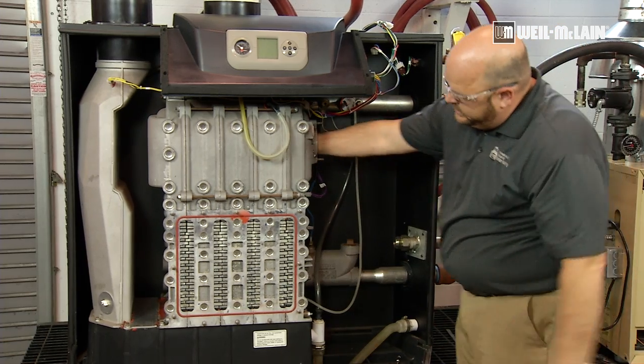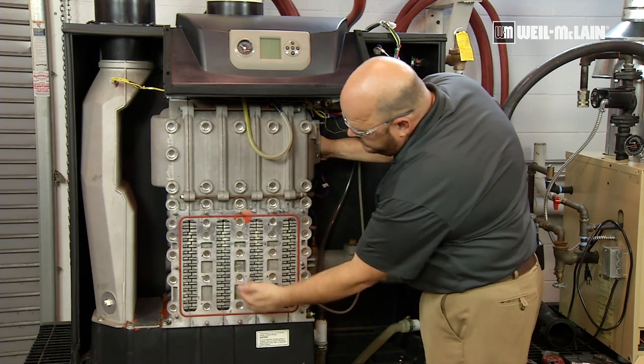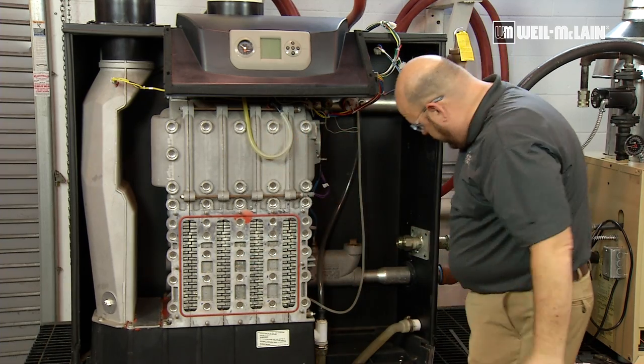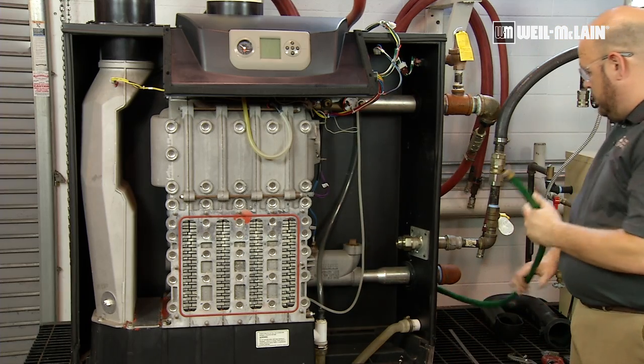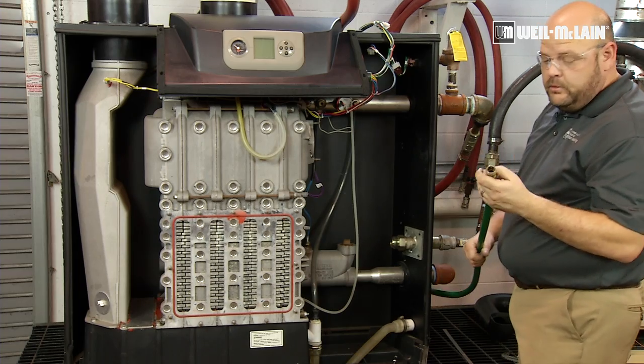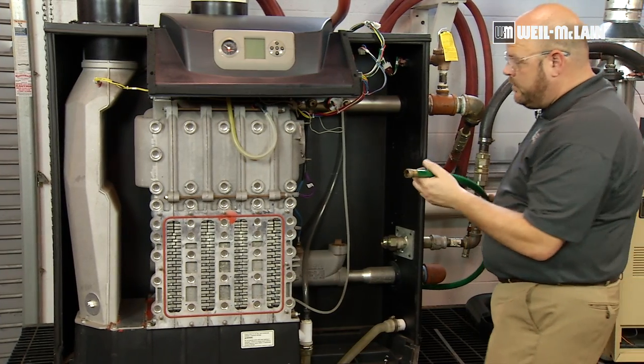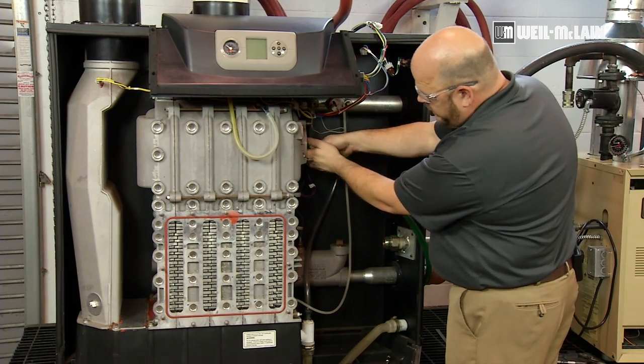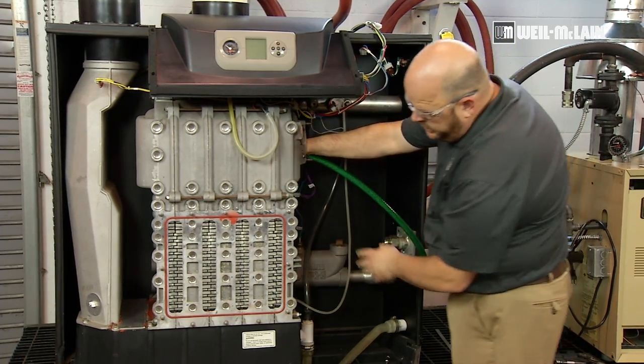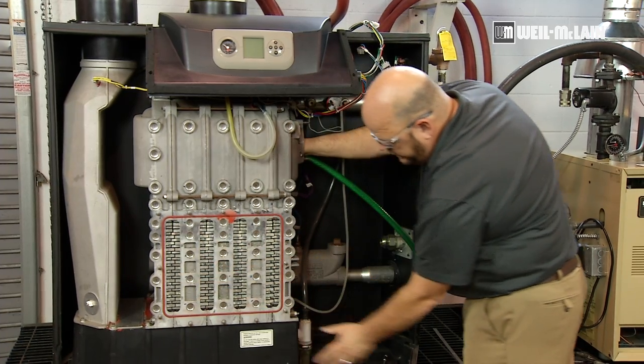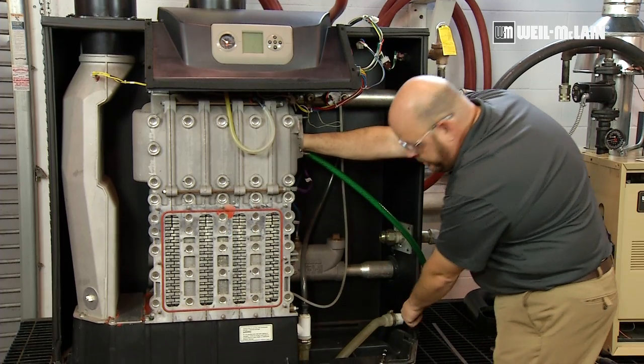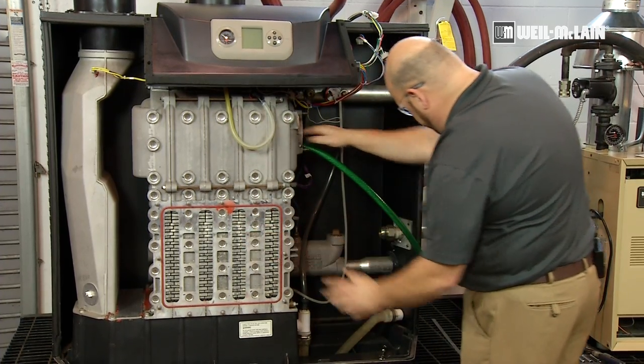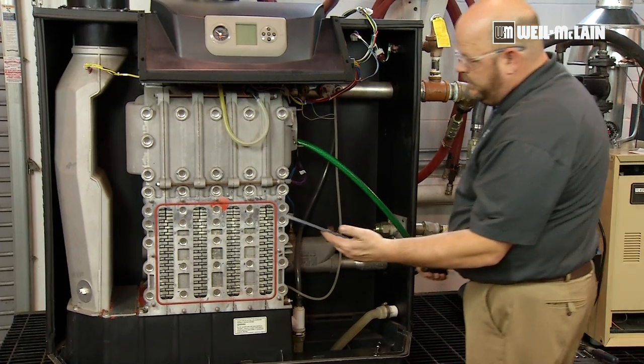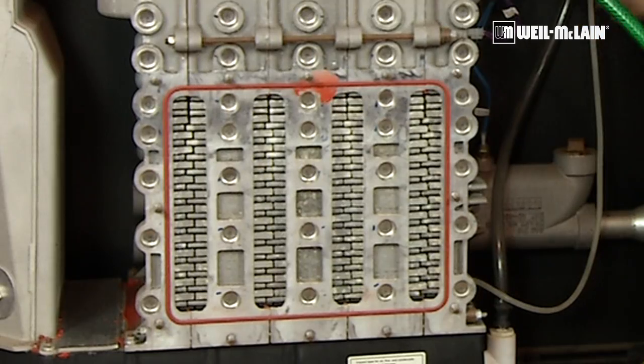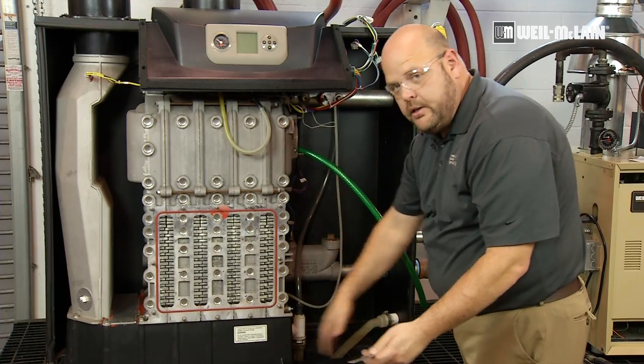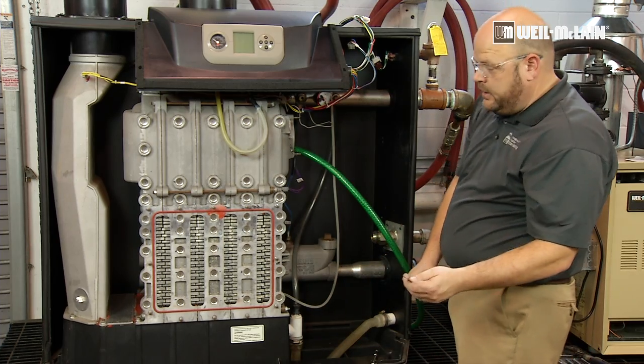Now that we're open from the inside, all of our flueways on the inside are open to us, and we will use a garden hose and low flow. We don't need to overpressurize the water coming into the boiler, and we can go into where the burner was on the top of the combustion chamber, and it will flow down between the pins in the collector and out through our condensate drain. But as we're cleaning with our cleaning tool, leave the water going gently, and it will aid in the cleaning of the debris out of the heat exchanger, and it will flow down through and out the condensate drain.